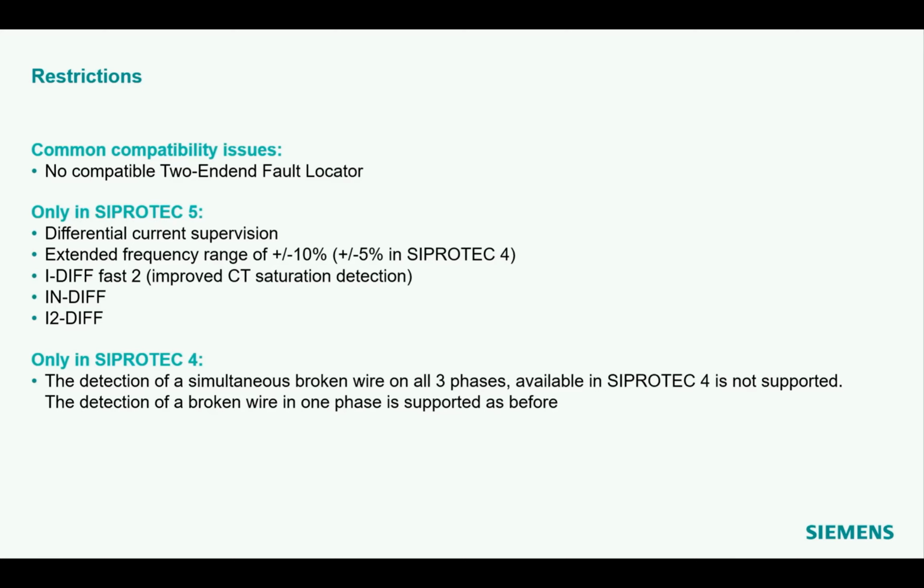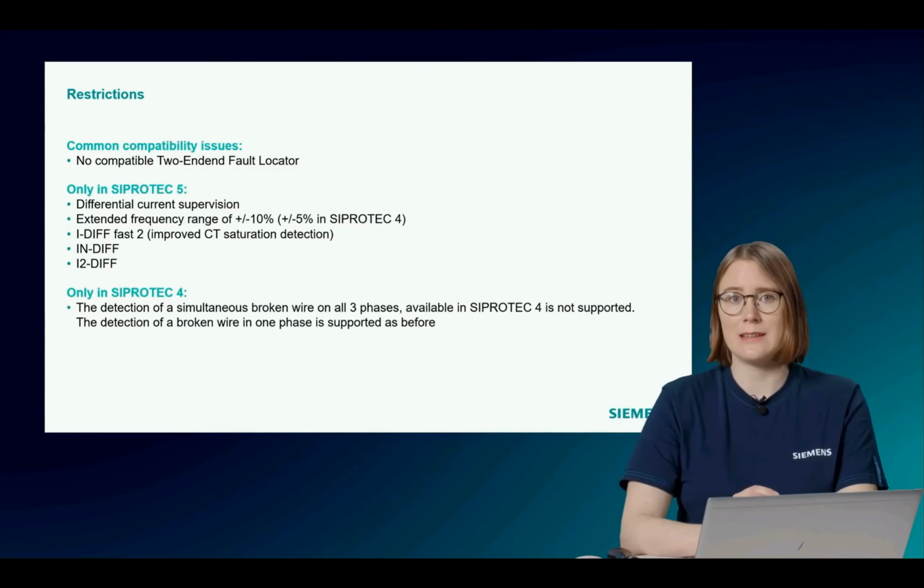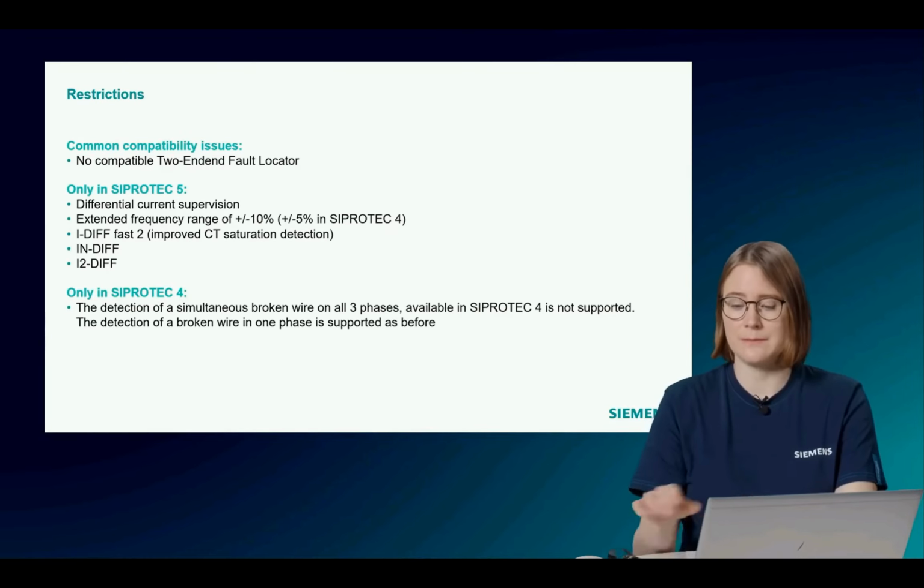Only available in SIPROTEC 4 is the detection of a simultaneous wire break on all three phases. In combination with SIPROTEC 5, only the detection of a wire break in one phase is supported.